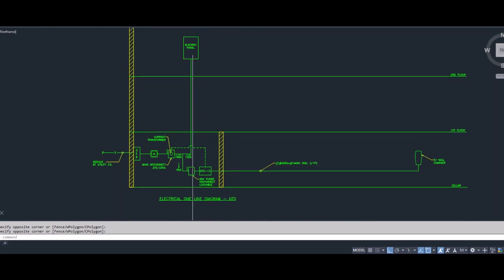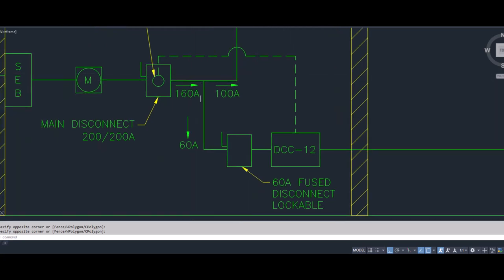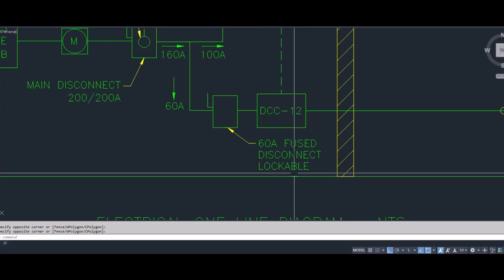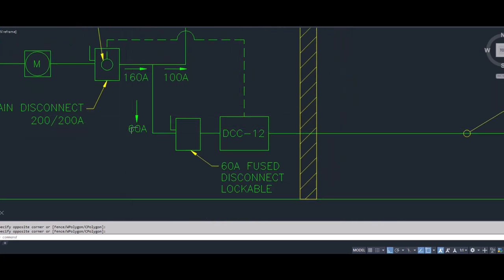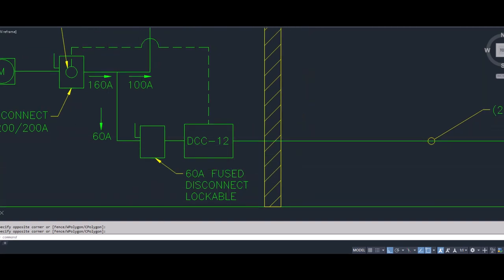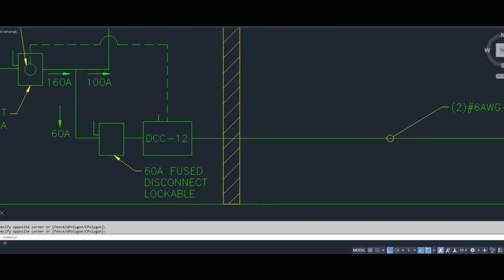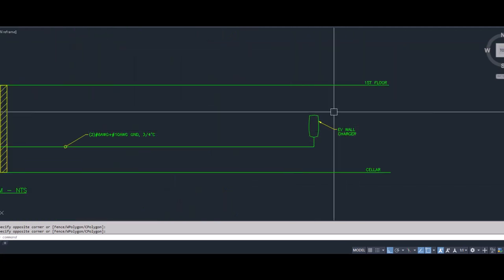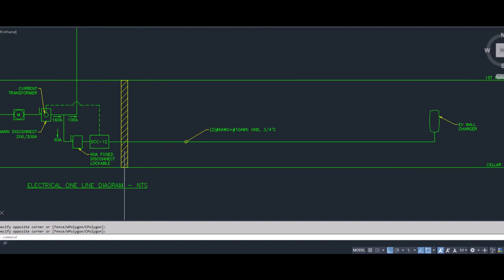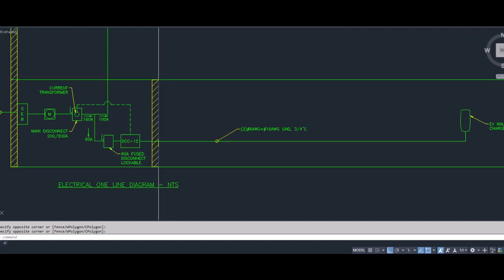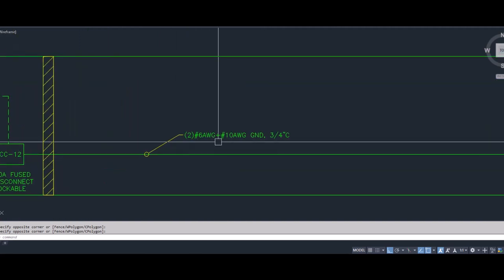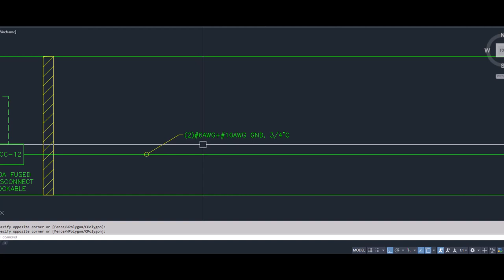So to get a circuit from this panel to the EV charger is not very ideal. It's too far. So you would basically use a system like this, where you provide a separate local fuse disconnect switch. In this example, it's going to a 60 amp EV charger. So the fuse is going to be at 60. And the part we're using is the DCC-12. And it goes to your EV charger, which can be close to this location or it could be hundreds of feet away. It doesn't matter. If it's more than 100 feet, you may have to size the wiring a little bit higher to account for some voltage drops from the long length of wiring.